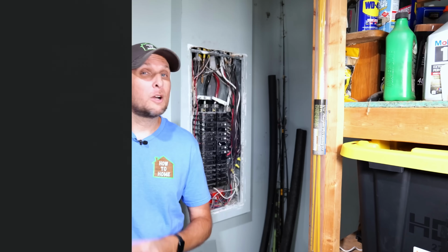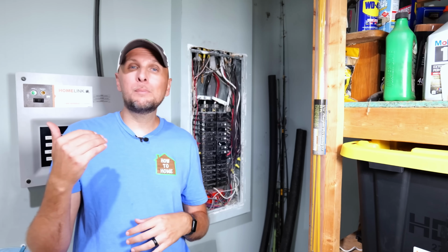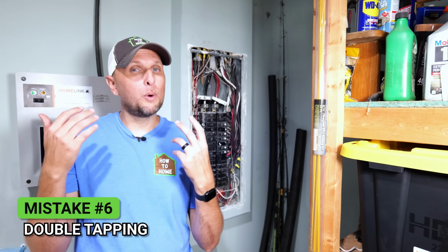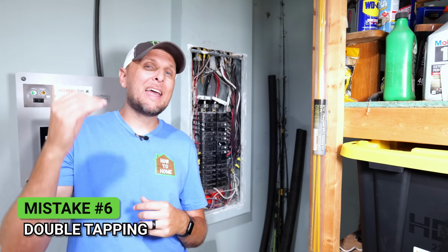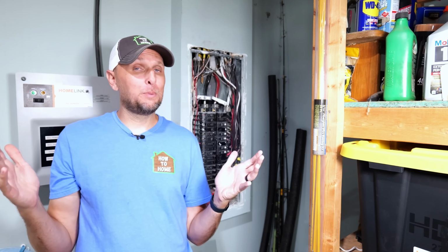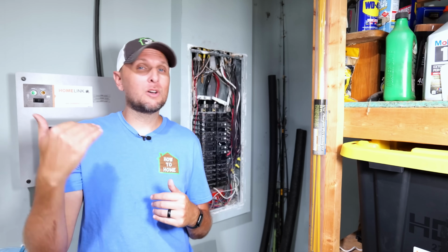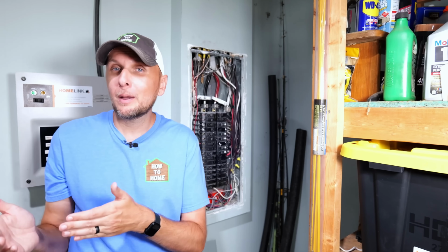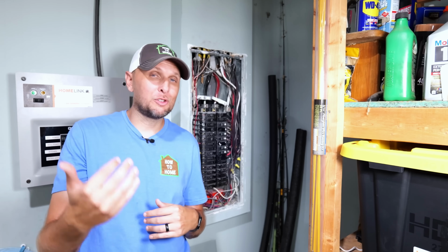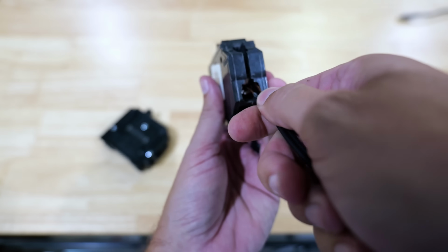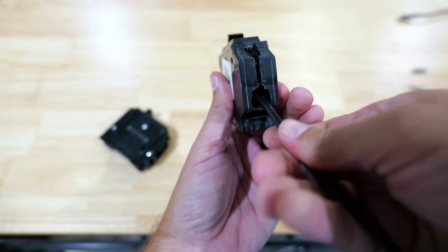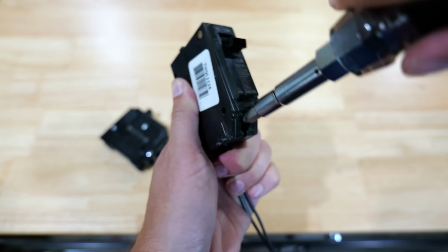All right, so for this next really big mistake, it comes down to double tapping, or putting more than one wire in a circuit breaker. And why do people do this? Well, for the same reasons that we talked about earlier when it came to overloading a panel. They're trying to add an extra circuit. They don't have room in their panel, so they think they can just add an additional wire into a circuit breaker and they're all covered.